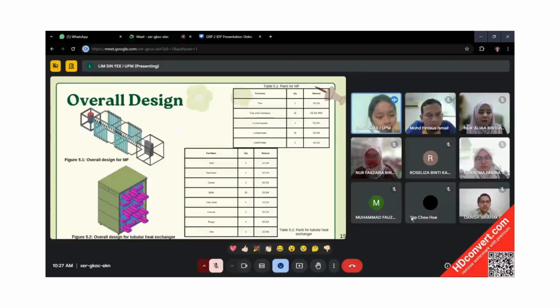And then figure 5.2 is the rough design for the tubular heat exchanger. There are 8 tubes there, and the baffles will be 20. It doesn't mean that more baffles in the heat exchanger is very good, because sometimes it will easily cause the fouling issue in the tubular heat exchanger. But a moderate number of baffles is good enough because it can allow the liquid to circulate in the tubular heat exchanger.